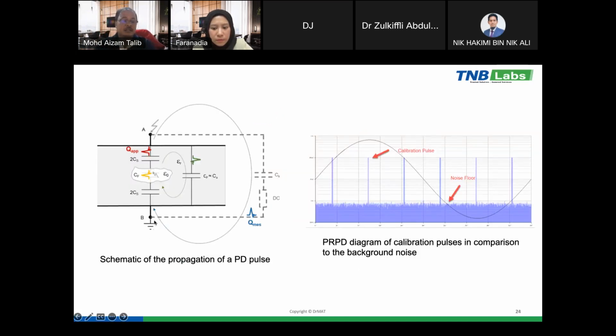Here is the schematic of the propagation of the PD pulse. Here we have the test object, and then, for example, we have a void in the test object. We inject a signal, and this signal combined with the PD pulse will travel to these measuring instruments. So when we have a phase resolved PD pattern, or phase resolved PD diagram, we are able to measure the calibration pulse.